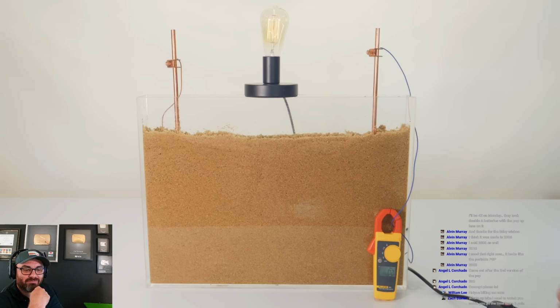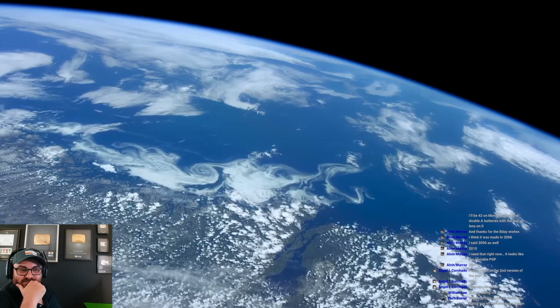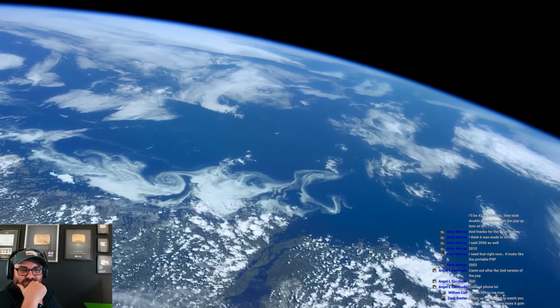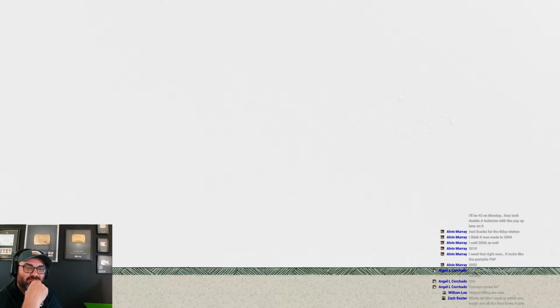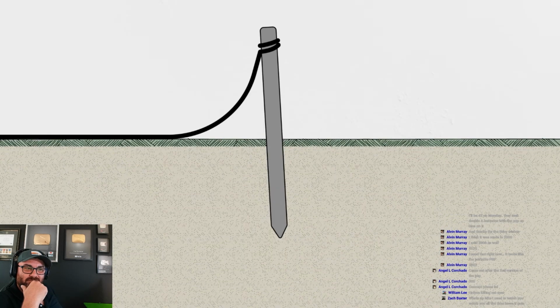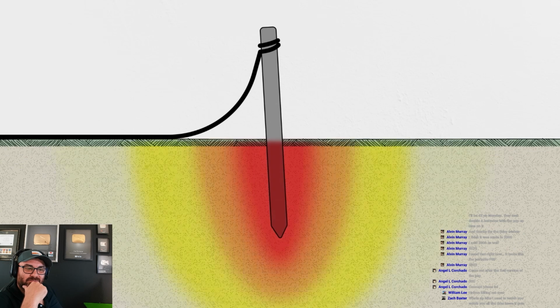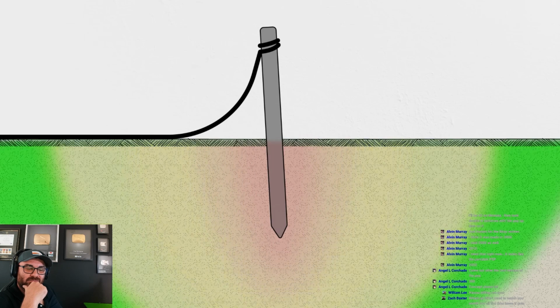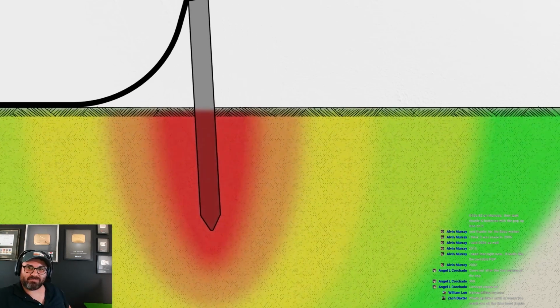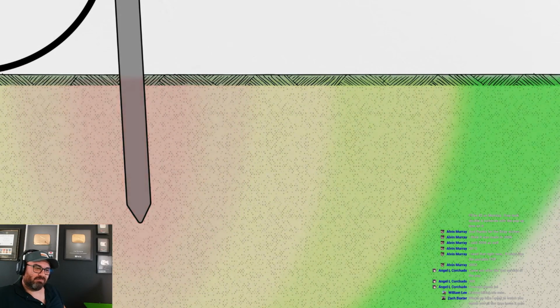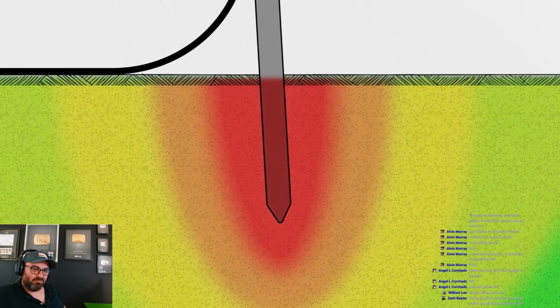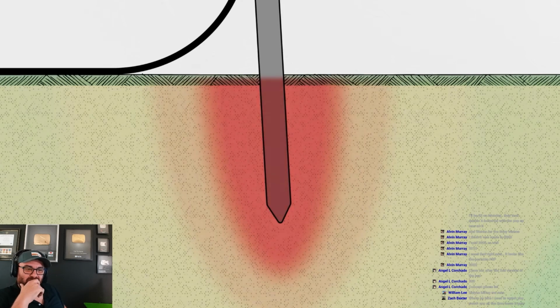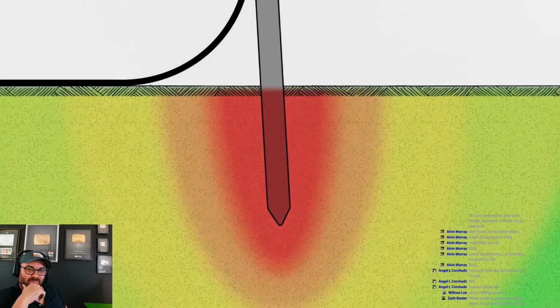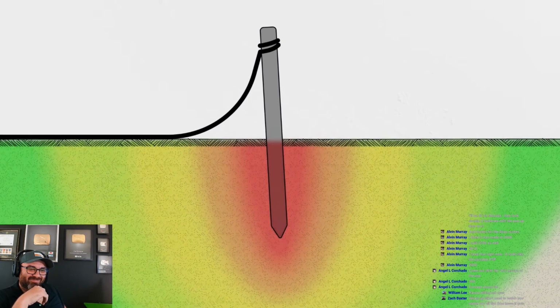This resistivity of soil to conduct current is pretty important. Earth isn't a great wire, but what it lacks in conductivity, it makes up for in size. You can kind of imagine current flowing from a ground electrode into the surrounding soil as a series of concentric shells, each representing a drop in voltage between the faulted conductor and the ground potential. Each shell has more surface area for current to flow, and so has lower resistance, until eventually there's practically no resistance at all. But up close to the electrode, the shells are spaced tightly together toward a single point or line. That spacing is related to the resistance of the soil, and it can represent a pretty serious safety issue.